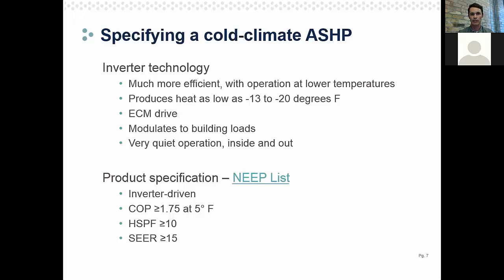So if you're looking to kind of find or differentiate one air source heat pump from another, and you're interested in finding cold climate heat pumps, here are some of the product specifications to look for. The key is that inverter-driven technology. And then you also want a COP, or coefficient of performance, of 1.75 at 5 degrees. And what that means is the system's able to operate efficiently at 5 degrees, so 1.75 at 5 degrees, or an HSPF above 10 and a SEER above 15.